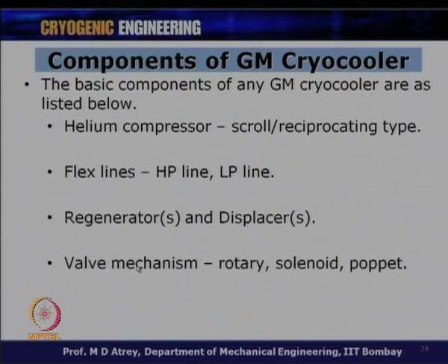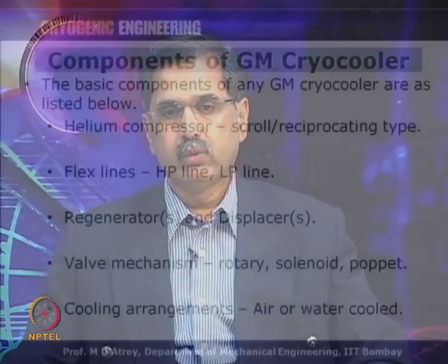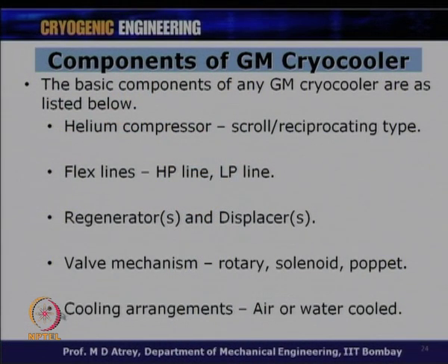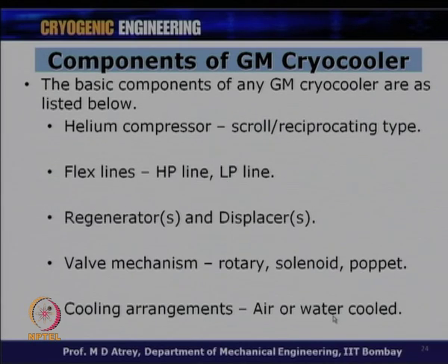The basic components of any GM cryocooler are: a helium compressor (typically scroll type), flex lines (HP and LP), the regenerator and displacer, the cold head, the valve mechanism (rotary valve, solenoid, or poppet), and a cooling arrangement for the helium compressor. The heat of compression is removed by chilled water at around 8–15°C circulated through the compressor. Some compressors are air-cooled.